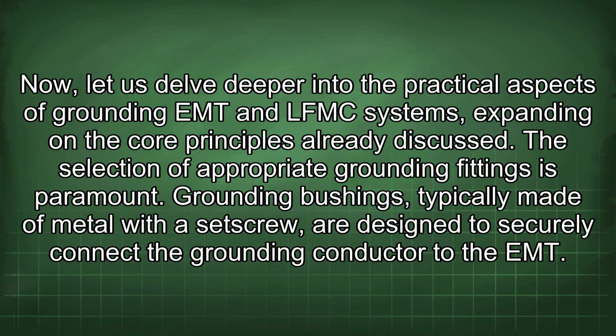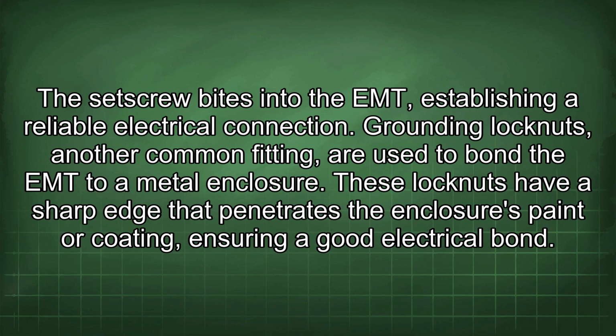Now, let us delve deeper into the practical aspects of grounding EMT and LFMC systems, expanding on the core principles already discussed. The selection of appropriate grounding fittings is paramount. Grounding bushings, typically made of metal with a set screw, are designed to securely connect the grounding conductor to the EMT. The set screw bites into the EMT, establishing a reliable electrical connection. Grounding locknuts, another common fitting, are used to bond the EMT to a metal enclosure. These locknuts have a sharp edge that penetrates the enclosure's paint or coating, ensuring a good electrical bond.